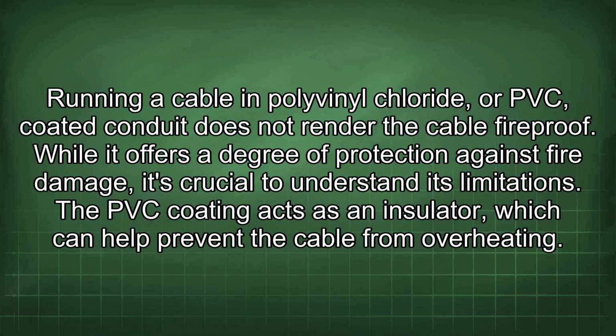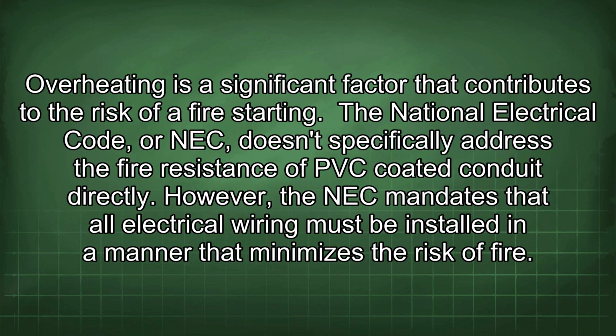Running a cable in polyvinyl chloride or PVC coated conduit does not render the cable fireproof. While it offers a degree of protection against fire damage, it's crucial to understand its limitations. The PVC coating acts as an insulator, which can help prevent the cable from overheating. Overheating is a significant factor that contributes to the risk of a fire starting.